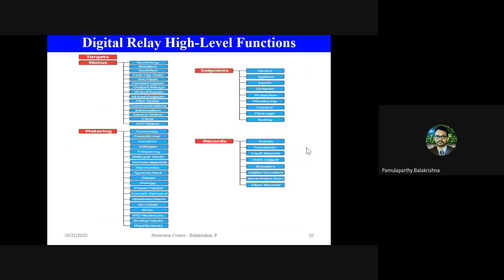So definitely he needs various data collected in the form of records, like voltage and current waveforms and various signal data collected during the fault, for the post-mortem or post-diagnosis analysis: why that fault has occurred, what the reason is, whether there is any problem in the system, whether there is any check that I need to do. So how does the operator know whether the trip or the fault that has happened is a genuine fault, a temporary fault, or a problem within the system itself? For all those analyses, he requires various data, and all that data is collected in the form of records by the digital relay.